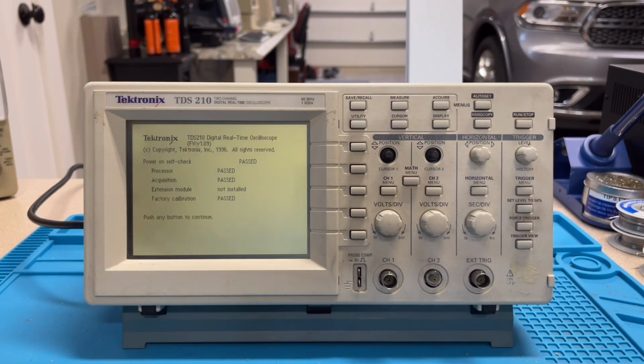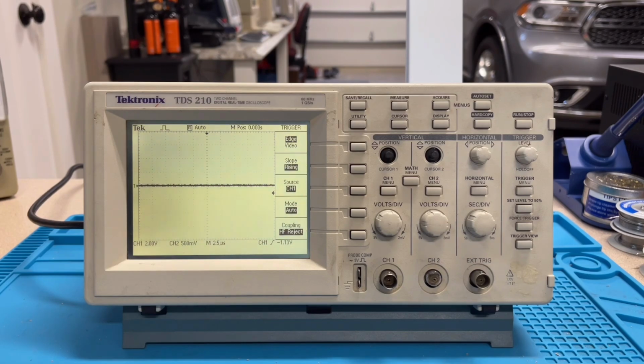Tektronix TDS210 digital real-time oscilloscope. All the tests passed, so it started up normally. Now the screens in these oscilloscopes are monochrome and they run off of a CCFL backlight which can dim over time. So it may be a little bit dimmer than you would expect. It's perfectly readable to my eyes, but in the service manual for these scopes, Tektronix does say that the backlight is a user replaceable part. So maybe sometime in the future I could replace the backlight with a new one and get more brightness out of these screens. But as you can see, the scope did come up and it is looking for a signal.